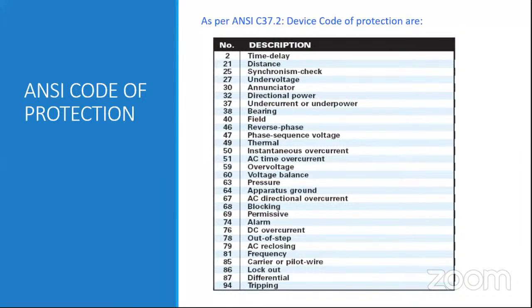59, over voltage condition, for over voltage protection. 60, voltage imbalance protection. 63, pressure for transformer, we can say this is used for the pressure gauge.